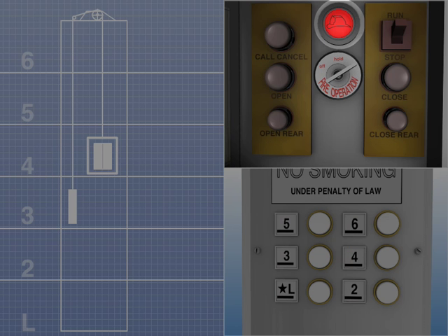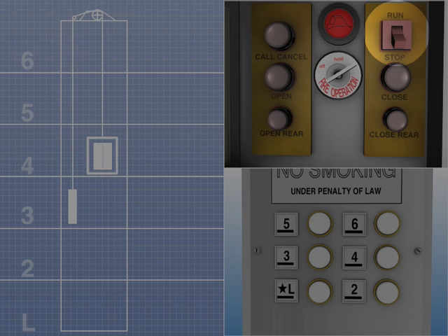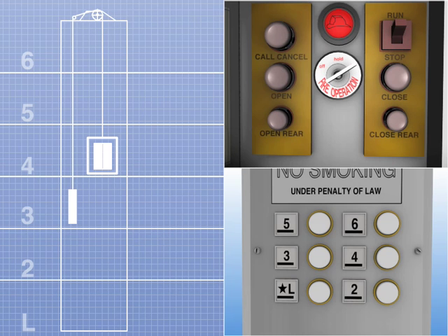The fire hat visual signal was first illuminated when the elevator was placed on Phase 1 elevator recall. Remember that it will remain illuminated until the elevator is returned to normal service. If the fire hat light begins to illuminate intermittently, it is a sign that an elevator machine room or hoistway smoke detector has been activated. This is a signal to the firefighters that the elevator may be unsafe to operate since the fire may have breached these enclosures.